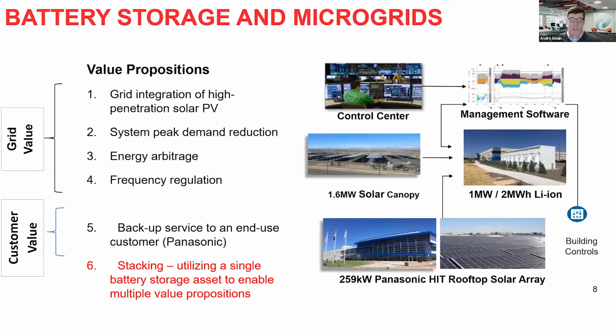I won't steal too much of our next speaker Dave's thunder here, but some of the value propositions we can get from battery storage include integrating a high penetration of PV, shifting load as Lester mentioned in his presentation, reducing system peak by dispatching batteries during hot summer days, energy arbitrage, and even frequency regulation, down to the sub-cycle use of the battery to control system frequency.